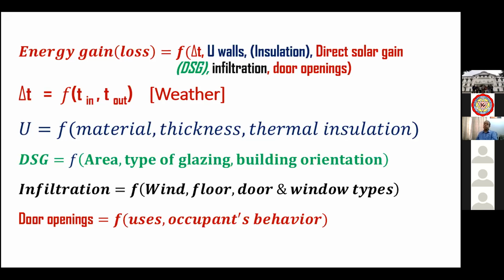That's a function of delta T, the difference in temperature between inside and outside. If we make delta T higher, we're increasing the energy loss, talking about winter. If outside ambient temperature is 2 degrees Celsius and we want to maintain 20 degrees inside, our delta T is 18. If we maintain 22, delta T is 20. If we maintain 24, delta T is 22.